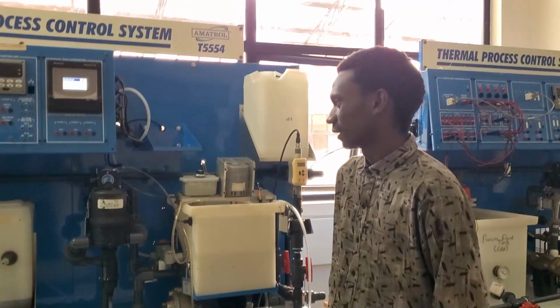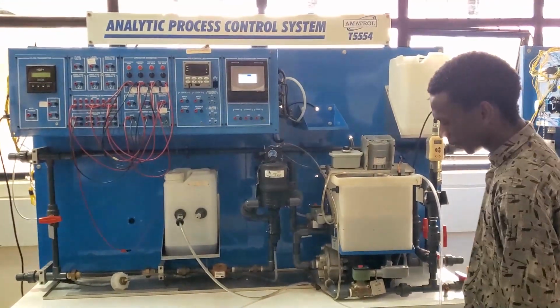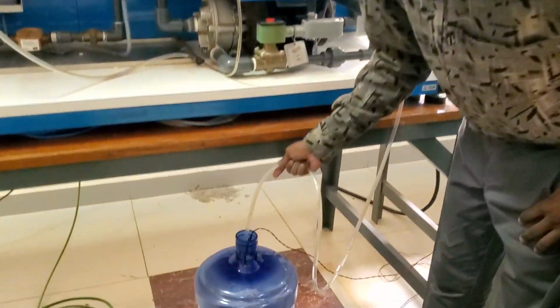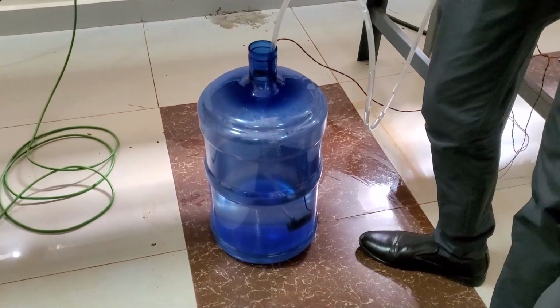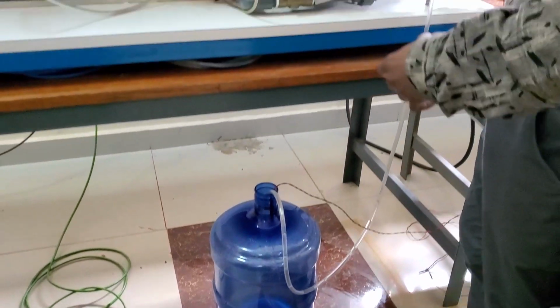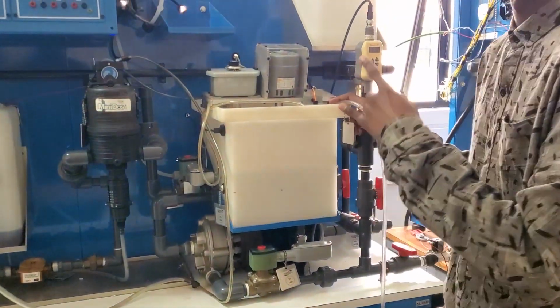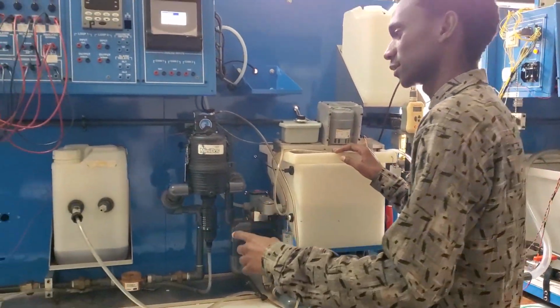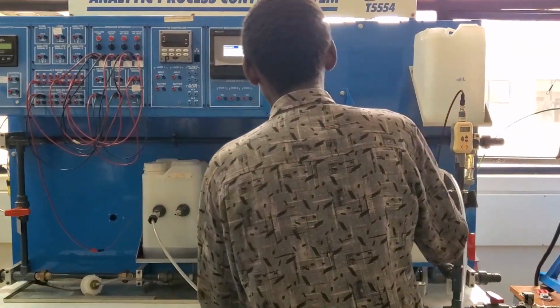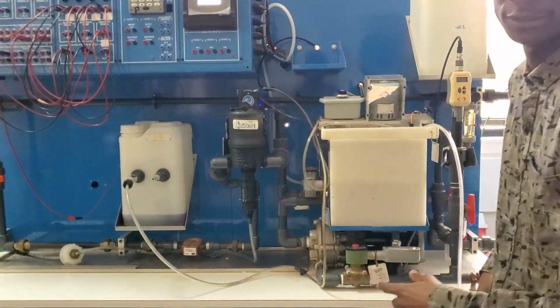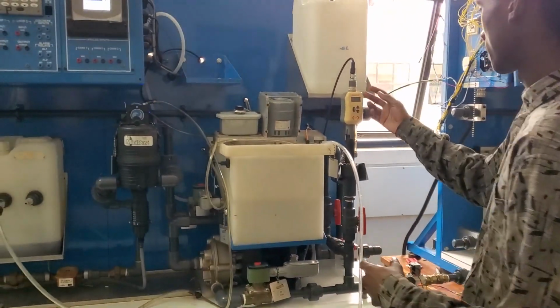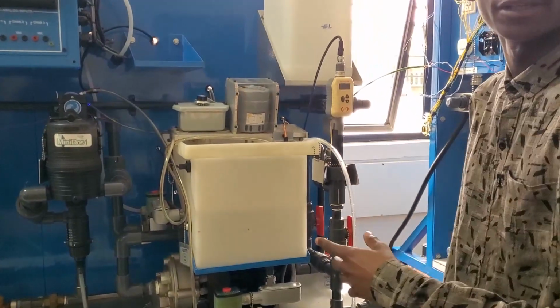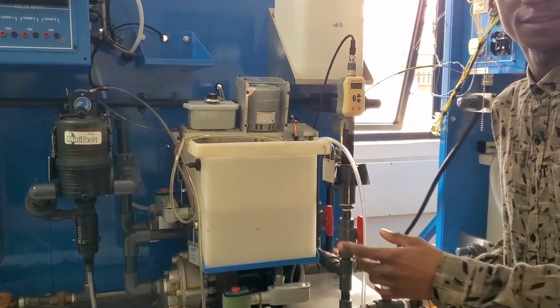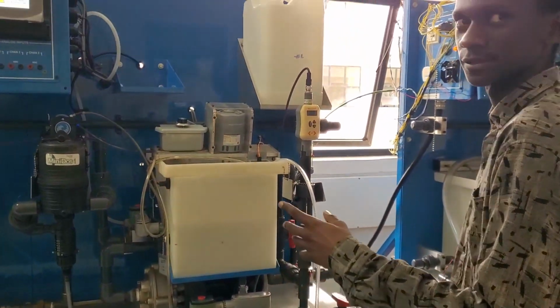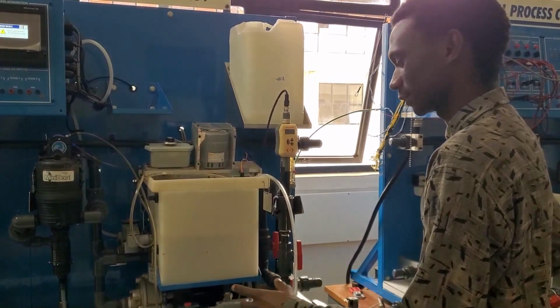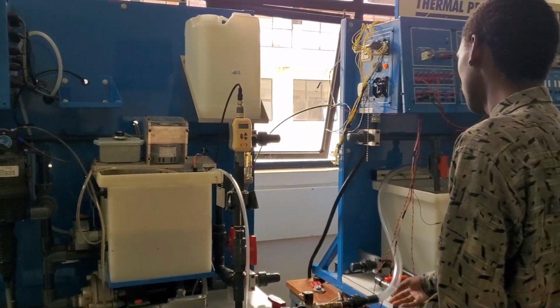So this is the analytical process station, whereby we have a submersible water pump that will be used to start the sequence. On the SCADA, the operator can start the sequence where we pump in water that will be used to dilute the concentrated calcium hypochlorite solution that's added in to manufacture the bleach.